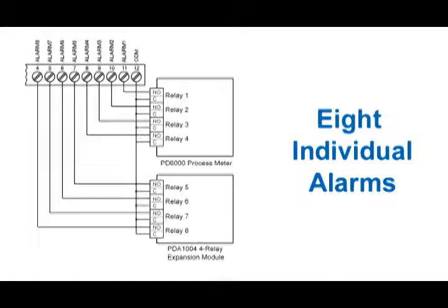And you can see that up here is the alarm in connector, and each one of these separate inputs has its own alarm in line. So relay number eight is connected to alarm in number eight. So whenever relay number eight trips, an alarm will occur on input number eight.